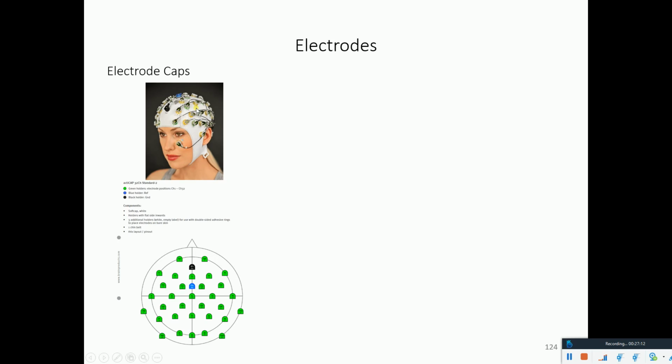And with 128 you have even more electrodes in between. But it's still referred to as the 10-20 system because these electrodes are essentially placed in the caps according to these old 10-20 rules. But from a practical perspective, it's a lot easier. You just adjust the Cz electrode so that it's midline between nasion and inion and between periauricular point left and periauricular point right. And then you make sure that the cap sits nicely, and then you plug it in.